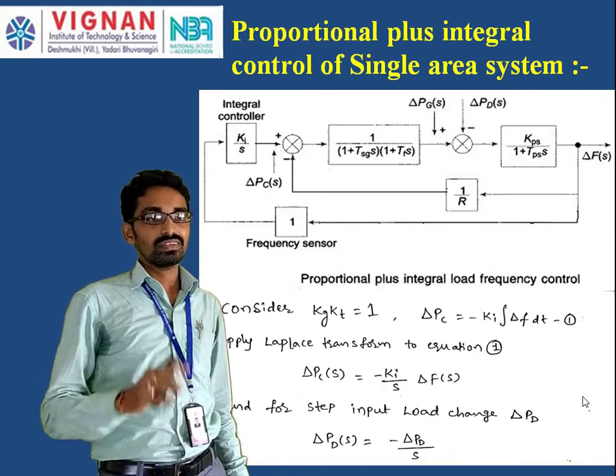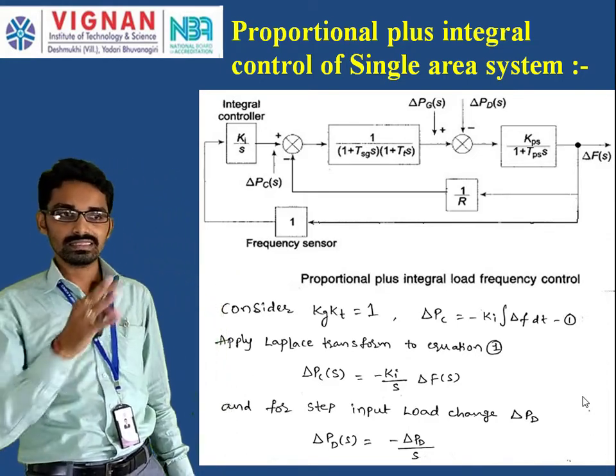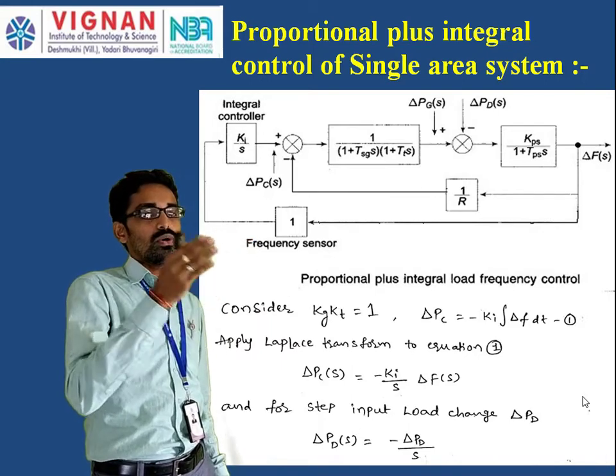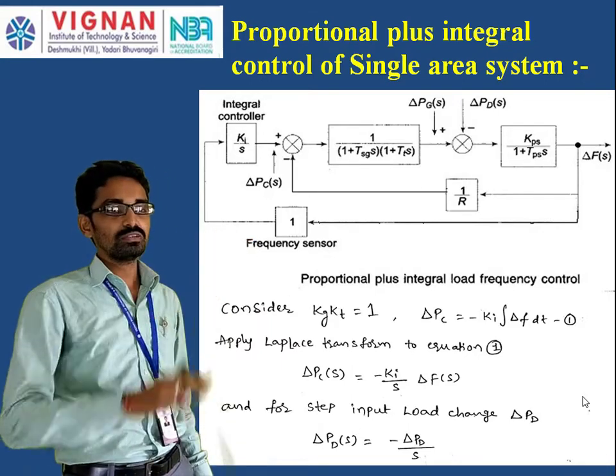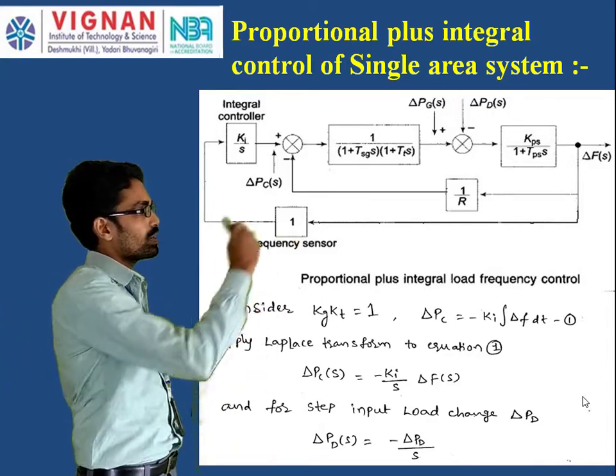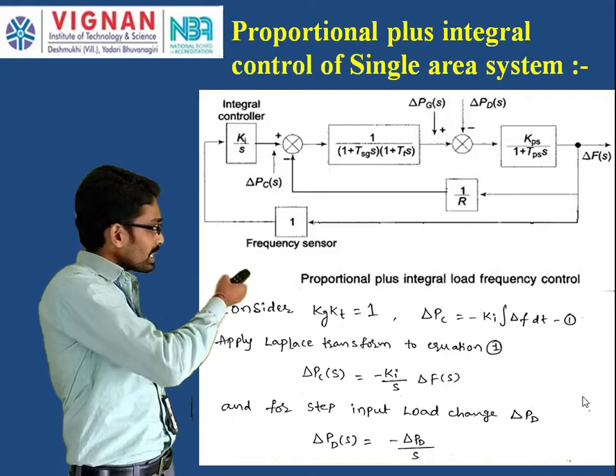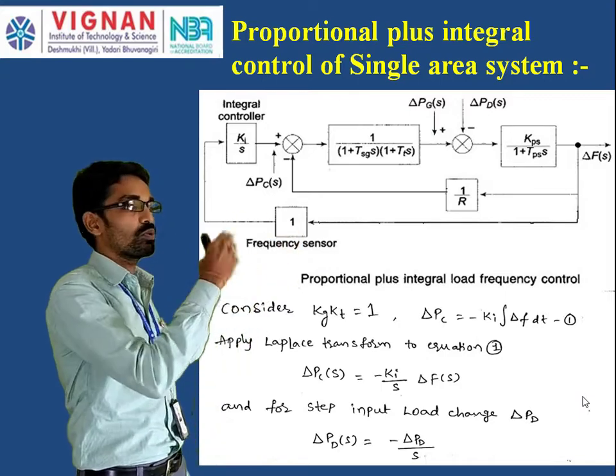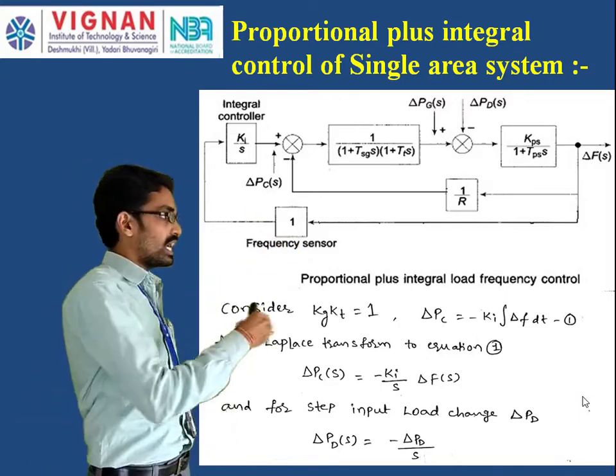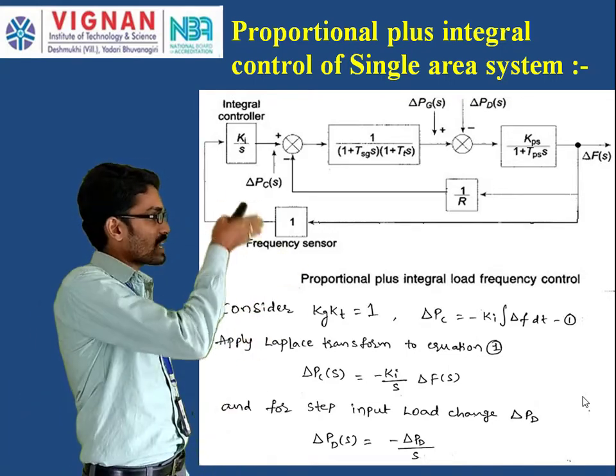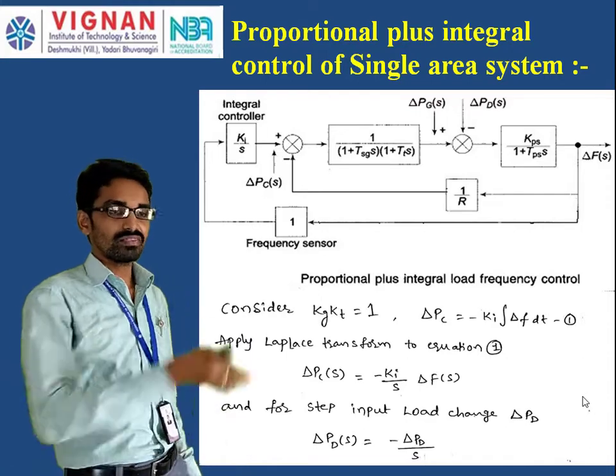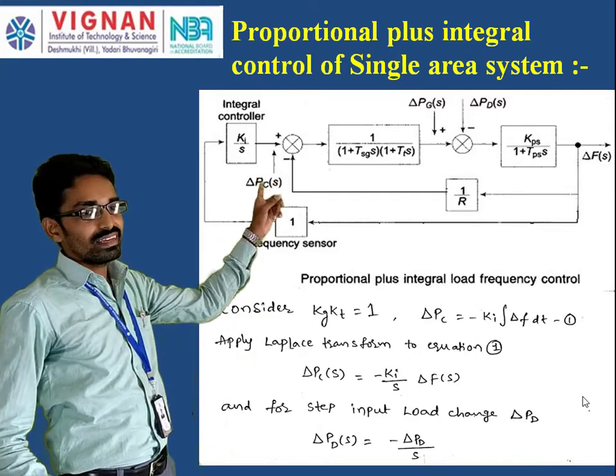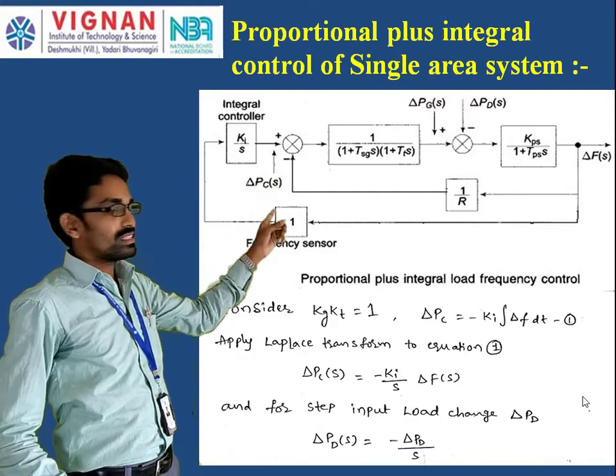That means we need to maintain the frequency between 48.5 and 51.5 Hz. If we change the load requirement, there is a large deviation in speed that will cause the frequency to move above the tolerated limit. In order to avoid that, we are going to reduce — or make — the steady state error of the frequency equal to 0 by introducing an integral controller, that is ki/s.